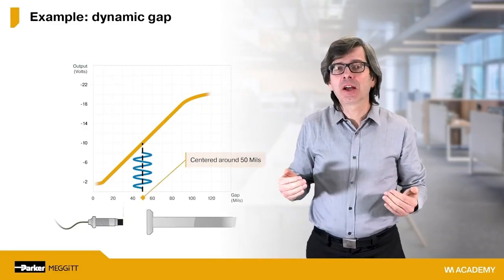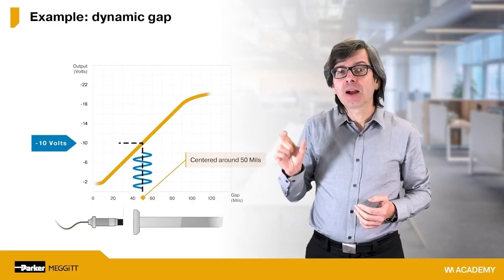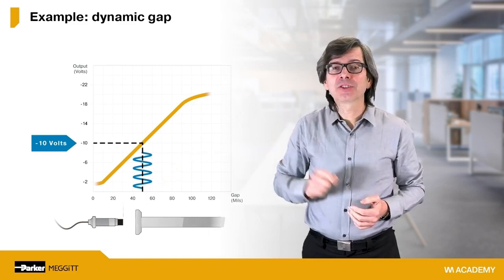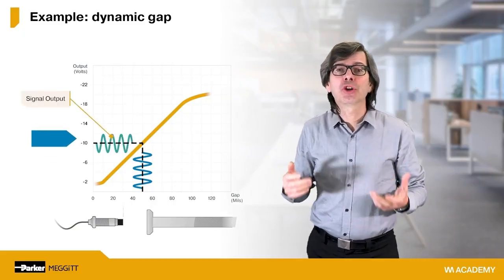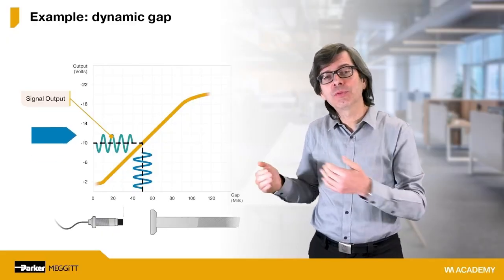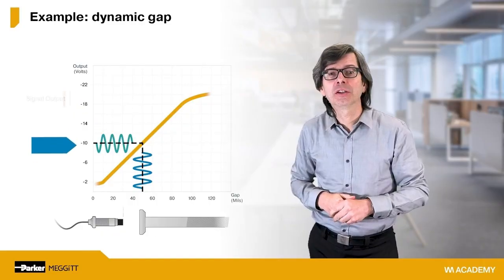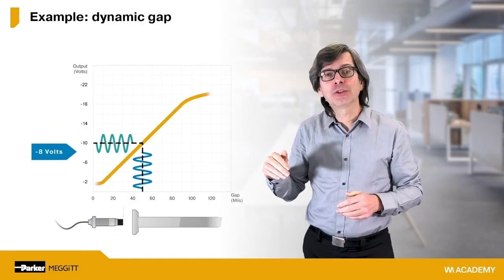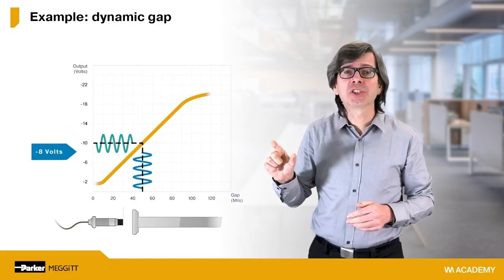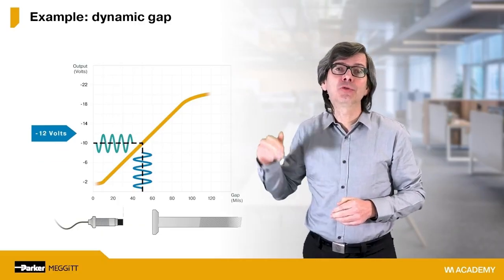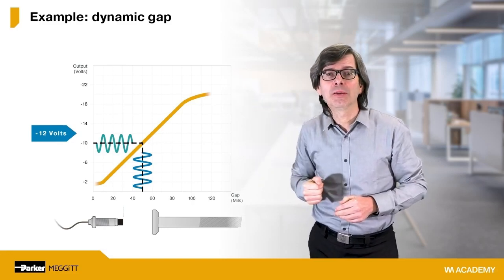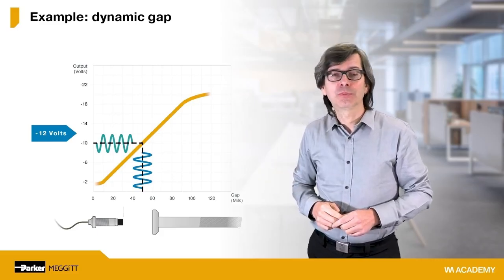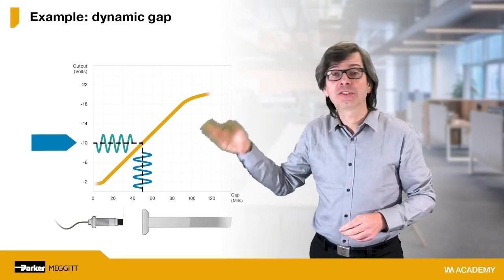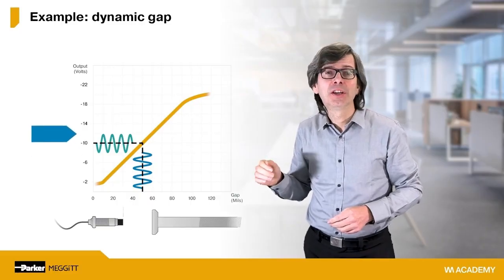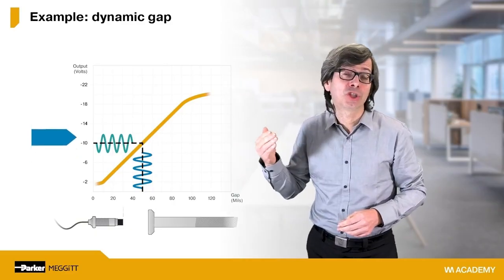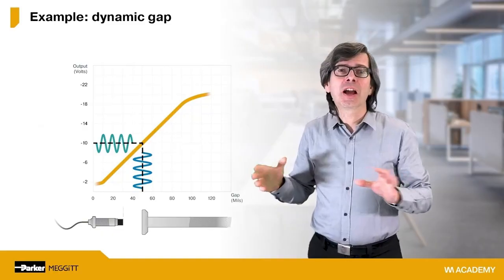This vibration is centered about 50 mils of gap, and this average gap would be observed on a voltmeter as minus 10 volts DC. This sinusoidal change in physical gap will result in an output voltage that is also a sinusoid, as you can see here in green color. When the gap decreases to 40 mils, the sinusoid reaches its minimum output of minus 8 volts. Then the sinusoid heads towards its other extreme at 60 mils of gap and minus 12 volts at the output. It then swings in the other direction, etc. The sinusoidal input, the changing gap, results in a sinusoidal replica at the output, which is a changing voltage. One is changing gap, the other is changing voltage.